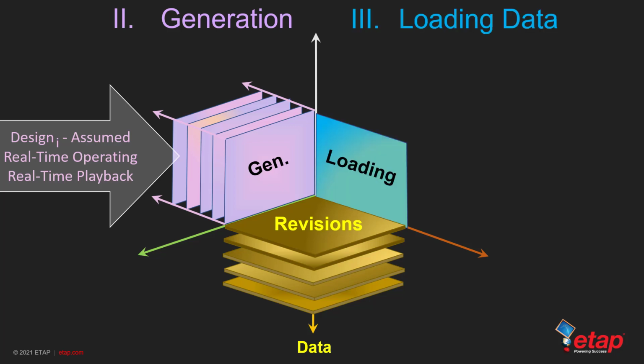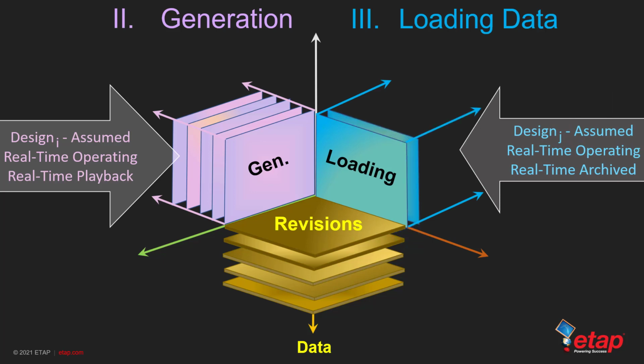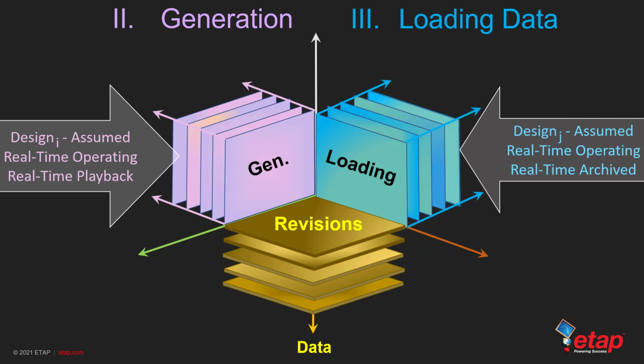The next element is loading data. For different studies you have different loading data: minimum loading, maximum loading, normal loading, emergency loading, and so on, each with different values. During design you don't have actual loadings, so you assume values and run a number of studies at different loading conditions, and you want the program to remember all these assumed loadings. In real time, you have operation, and then you have archive data to bring up and see what has been operating before, for both loading and generation.